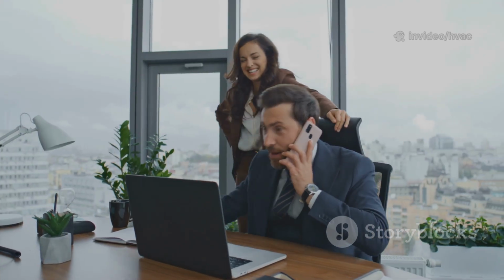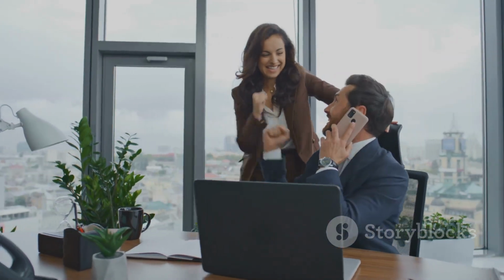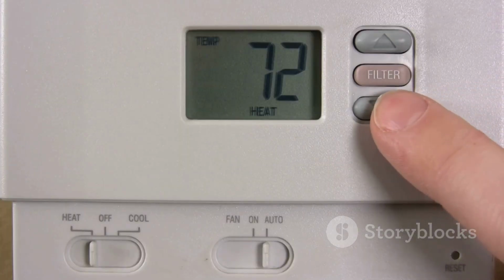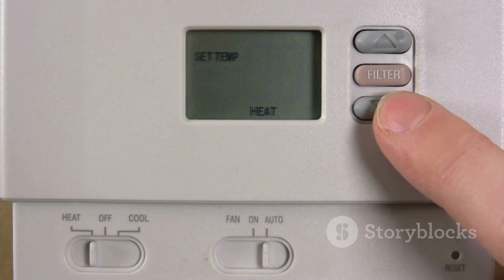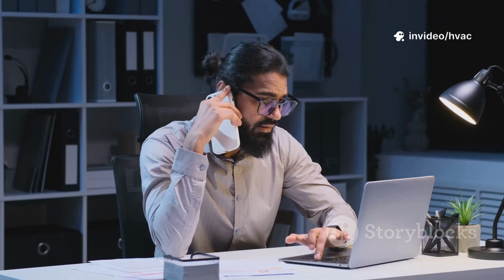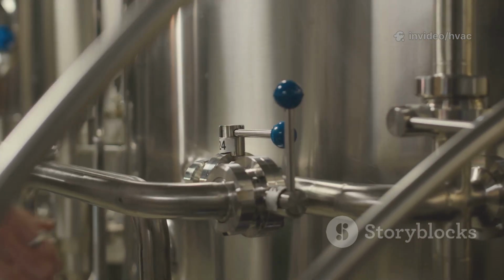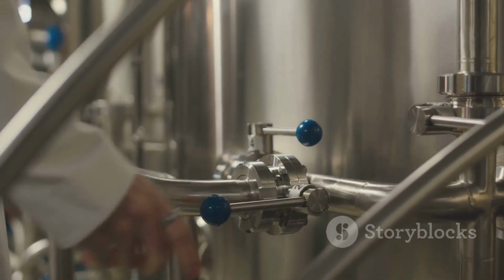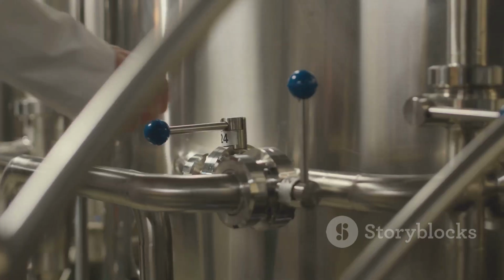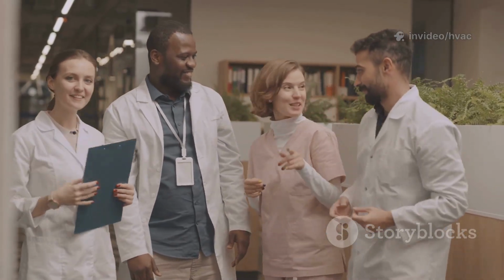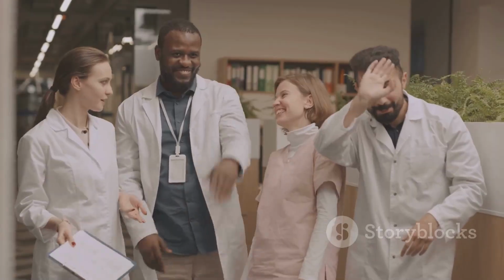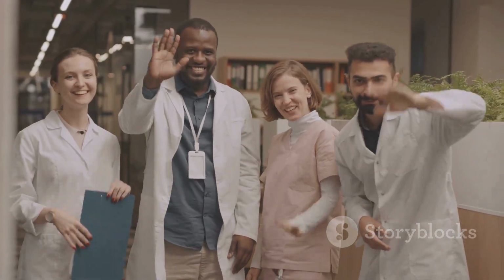Another lasting benefit is the superior comfort provided to the building's occupants. Unstable flow in traditional systems often leads to temperature swings, with rooms becoming too hot or too cold. This problem, often called hunting, is a common source of complaints. PICVs eliminate this issue by delivering a precise and steady flow of water to each terminal unit, regardless of pressure changes elsewhere in the system. This results in stable and accurate temperature control in every zone. A comfortable environment leads to happier and more productive occupants, whether they are office workers, hotel guests, or hospital patients, adding significant value to the property.